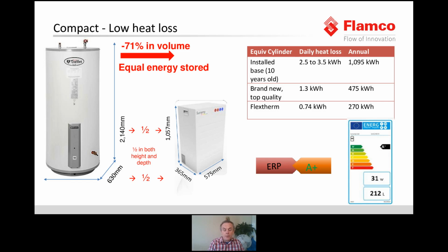And in terms of ERP, there are also additional benefits too. So as we know, ERP determines efficiency on direct cylinders with regard to standing heat loss. This has been recognized in SAP for years as being the most important facet of a cylinder in determining efficiency. The standing heat loss is that measurement calculated either in watts or kilowatt hours per day. ERP gives performance bands within which the heat loss of every cylinder will fit, thus determining the energy rating. Experience in the boiler and white goods industries has shown that customers are looking for and are prepared to pay for superior energy ratings. So products must be at worst C, and a new band of A+, which these products fit, has been introduced to encourage manufacturers to further enhance their products.